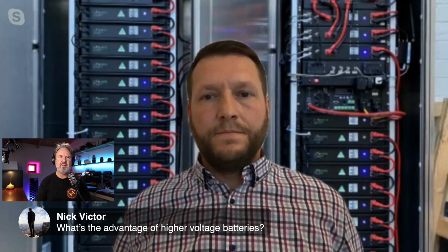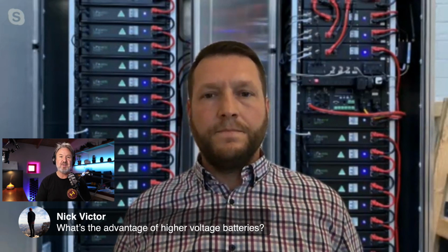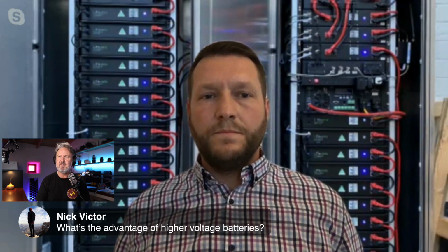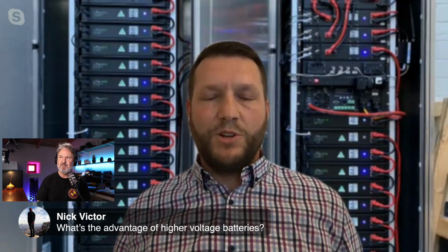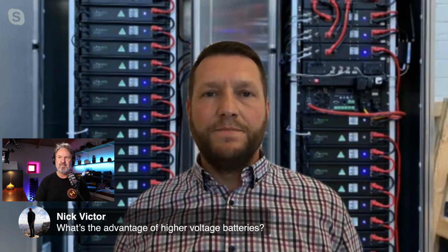Also, cable size and costs go down if you're not using 70 or 120 mil cable. So it depends on the size of the solution you're hooking up to, because the other thing to consider is that at 48 volts, it's ELV, but at 500 volts you have a different set of regulations and rules about who's allowed to work on the system. So it depends on the size of the application as to whether your focus is on current or voltage.